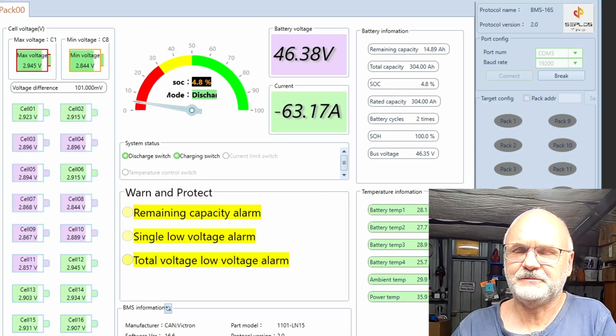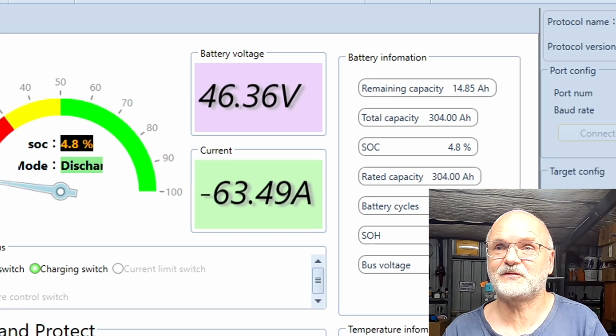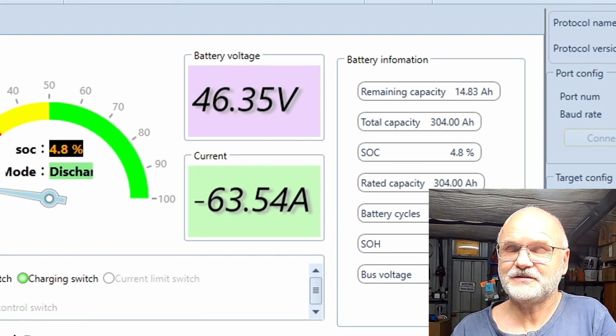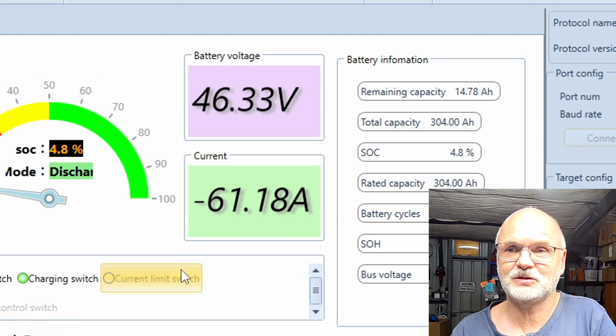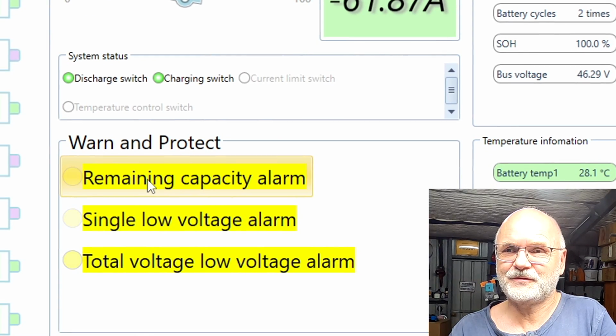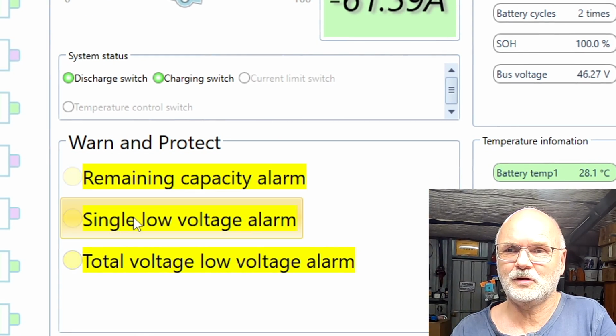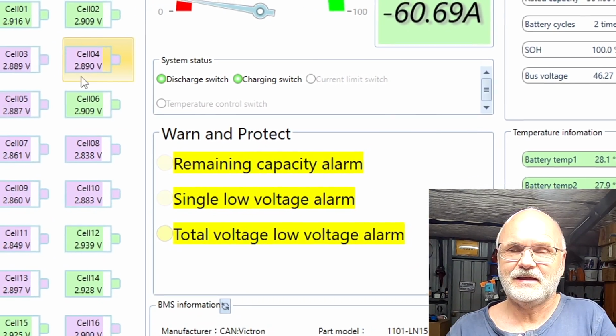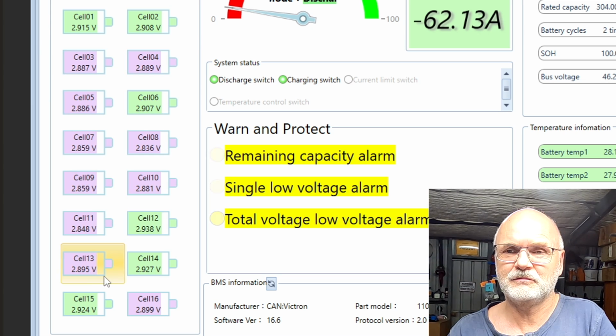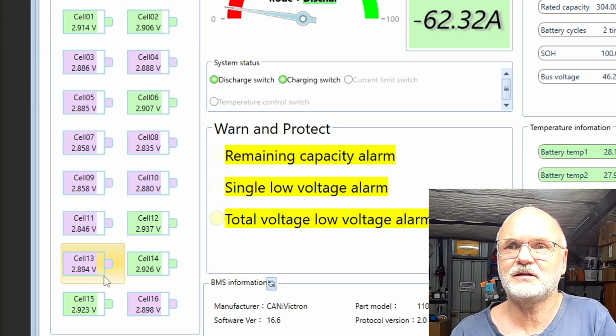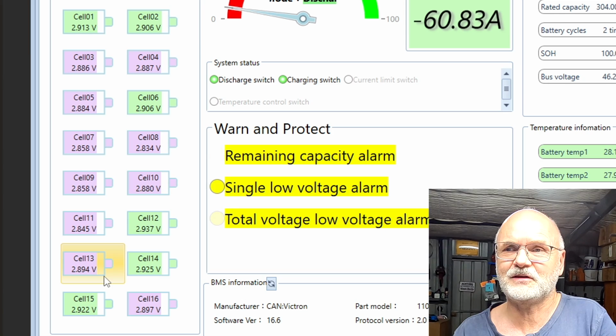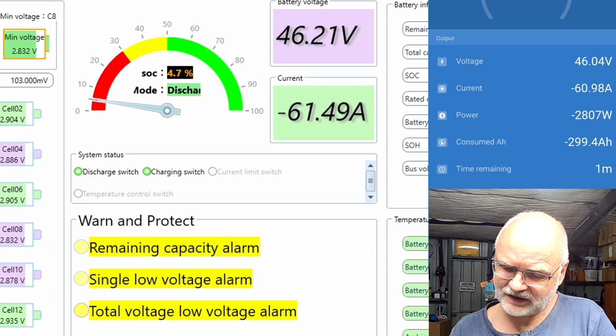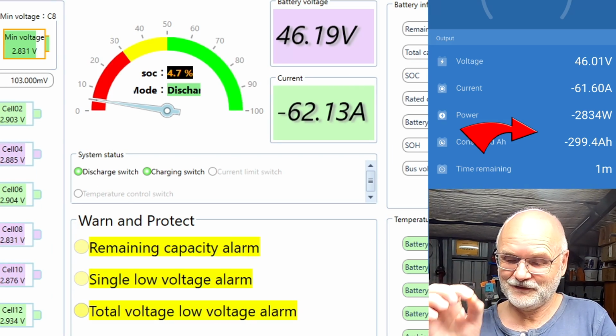Shortly after 11, we are still discharging this battery. 46 volts, at 63 amps we are discharging. We've got all the alarms: remaining capacity, single low voltage, total low voltage. Several cells are under 2.9 volts, I think, that's what the alarm is set to. We have discharged 300 ampere hours so far.